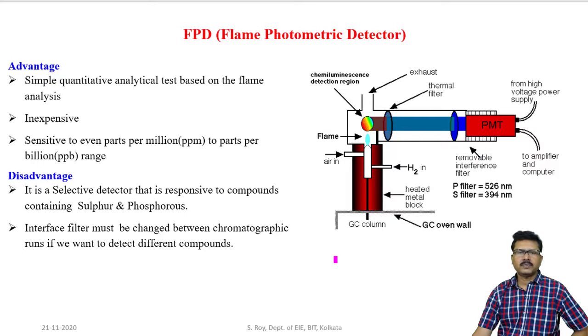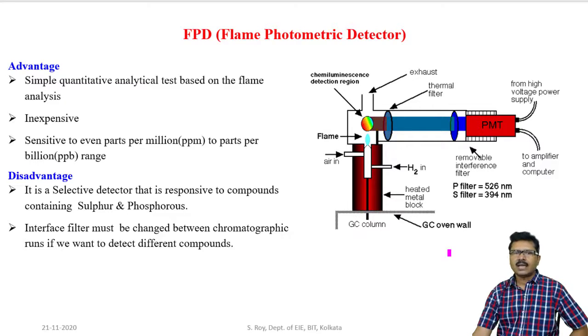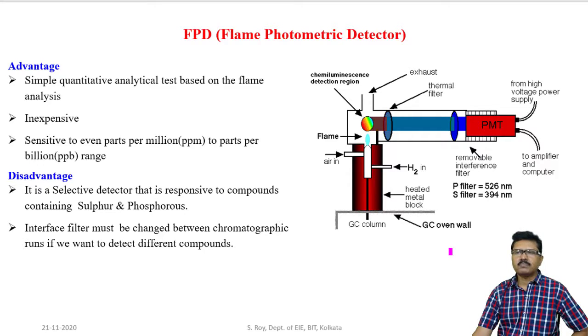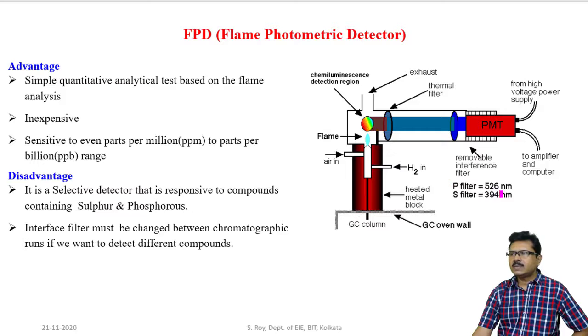Advantages of flame photometric detector: it is very simple, gives quantitative analytical test based on flame analysis, is inexpensive, and sensitivity is very high — even in parts per million to parts per billion range. Disadvantages: it is very selective to phosphorus and sulfur only. Another disadvantage is that the interference filter must be changed between chromatographic runs if we want to detect different compounds — when detecting sulfur a corresponding filter is used, and for phosphorus, the filter must be changed to allow 526 nanometer light energy.